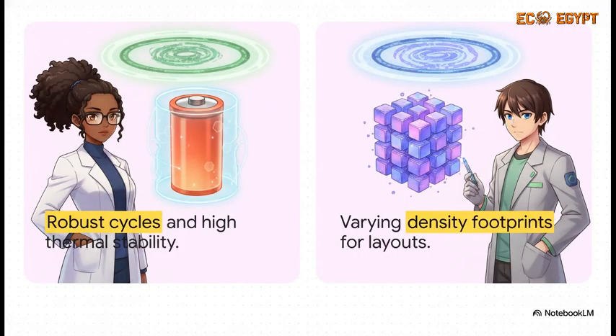But before we even think about running the numbers, we have to pick our chemistry. Chapter 3.3 lays out this critical comparison between lithium iron phosphate, LFP, and lithium nickel manganese cobalt, NMC. Why does this matter? Well, it literally dictates your thermal limits, electrode wear, and your total life cycle costs. Generally, LFP is going to give you those robust cycle counts and thermal stability we just talked about, whereas NMC might give you a slightly different density footprint.